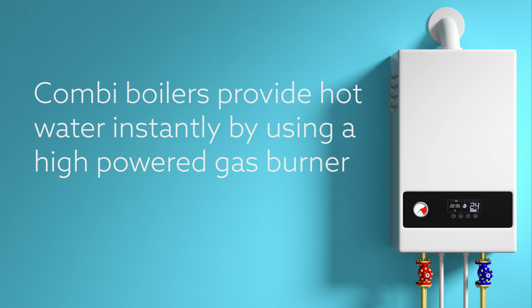Many people are familiar with domestic combi boilers. These produce hot water instantaneously, usually by using a high-powered gas burner. Although modern condensing combi boilers often have really impressive efficiency figures of 92% or more, those figures tend to apply to the space heating part of the boiler, and for heating water, the efficiency is often much lower.